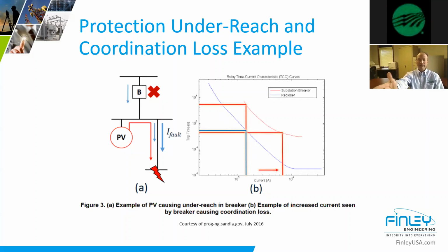So in my example A, if you see here, we've got breaker B and PV system noted. Now, if we show the fault where I've got the nice little lightning bolt, normal fault current magnitude would be in blue, so you'd see fault current through breaker B feeding into the fault, I fault that I'm calling there in figure A. And look at the typical coordination in blue over on the graph, or purple, it's kind of. You see that recloser's ability to coordinate, and that fault current and its time to trip, and its ability to stay in coordination with the downstream regulator. Now notice what could happen in this potential.